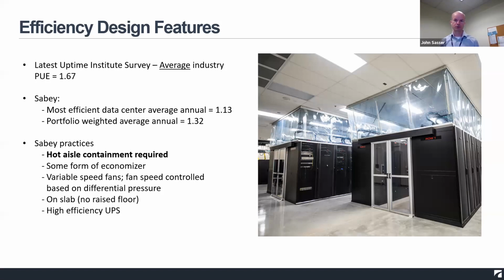So for really 10 plus years, more like 12 years, we've had some practices in place to achieve those sort of efficiency numbers. Back in 2008, the first data center that we actually designed ourselves, as opposed to working with the customer on their design, we required hot aisle containment. And we've required hot aisle containment in all of our new data center designs since then. The airflow management is really important in obtaining very good efficiency numbers. In all of our data centers since 2008, we've put in place some form of economizer. Cooling tends to be the second largest load after the IT in terms of the energy used at a data center, so it's very important to use it efficiently. Economizer essentially lets you cool the IT equipment without using mechanical cooling.